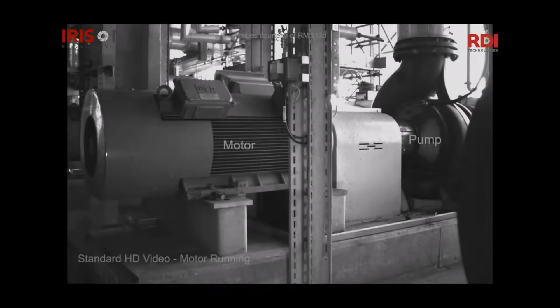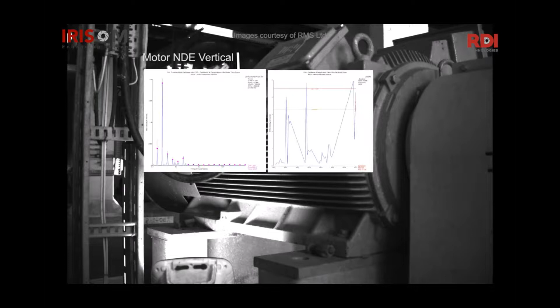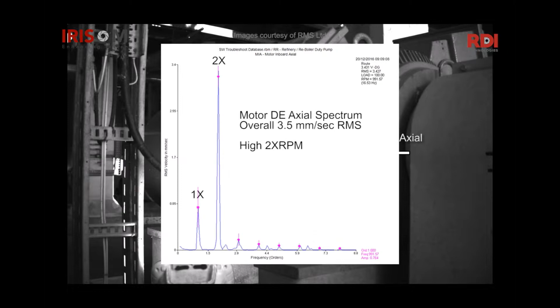Okay, so let's talk about complementary route-based methods. In a lot of facilities, you might on a regular monthly basis walk around and collect data, and you might have an alarm go off telling you there's an alert on a motor or pump or an asset, that the vibration levels have gotten high enough that you might want to investigate what's going on. So this is a motor pump that has a history of high 2 times vibration, and it was intermittent, but you saw the levels there over the history.